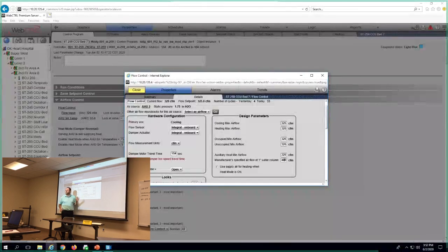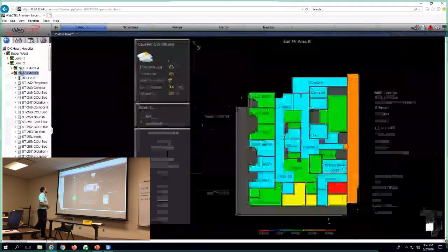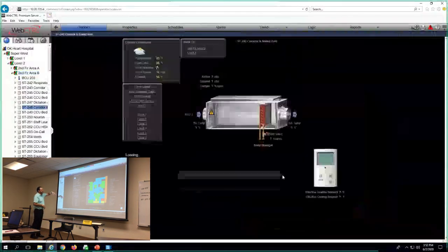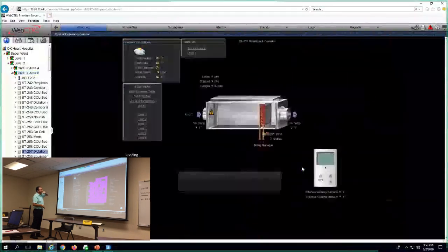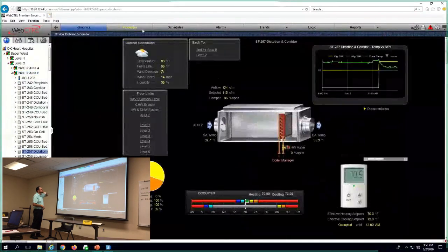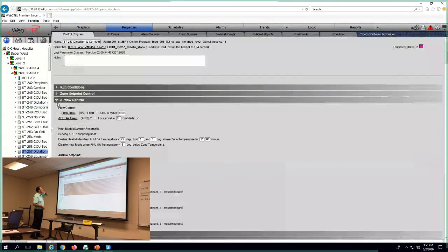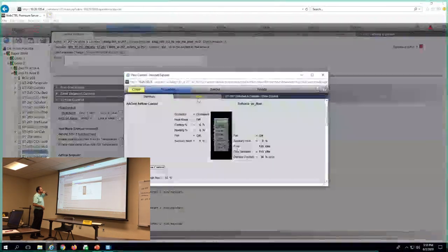When the temperature in the space drops below the heating set point, the VAV goes to this auxiliary min heating airflow set point. Let's go find another VAV that's got different numbers, because that's a constant volume VAV box. Let's go to like, it's probably a corridor VAV or something. Click on the one next door to it. Yeah. So go back up to properties. Airflow control. Yeah. See there, it's a little different.